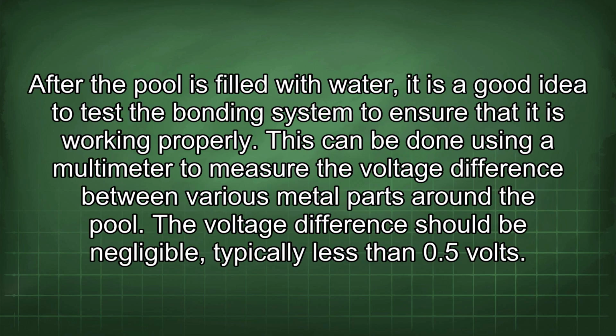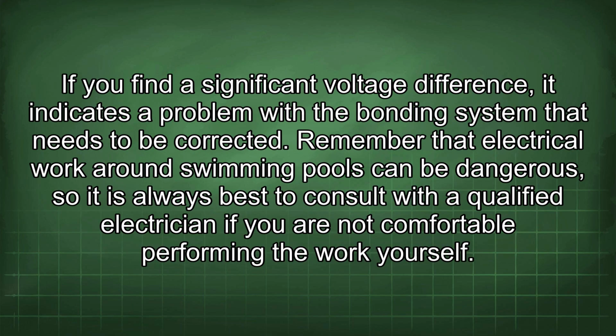After the pool is filled with water, it is a good idea to test the bonding system to ensure that it is working properly. This can be done using a multimeter to measure the voltage difference between various metal parts around the pool. The voltage difference should be negligible, typically less than 0.5 volts. If you find a significant voltage difference, it indicates a problem with the bonding system that needs to be corrected.